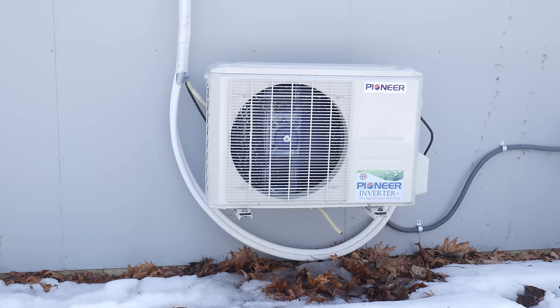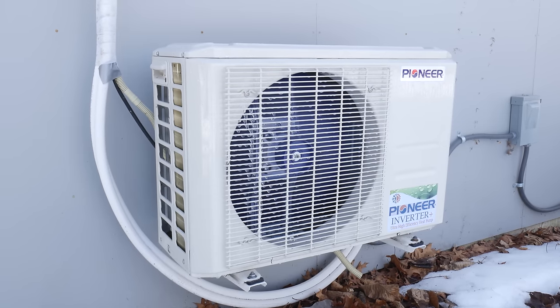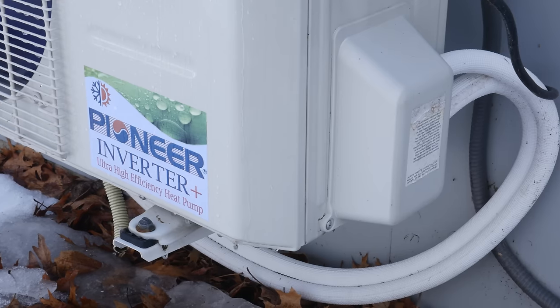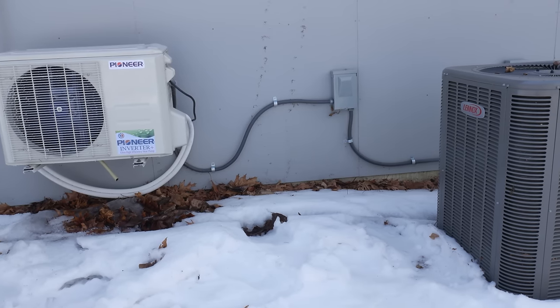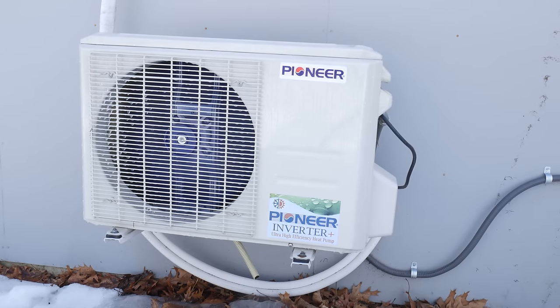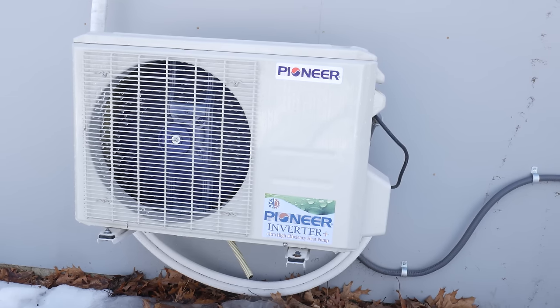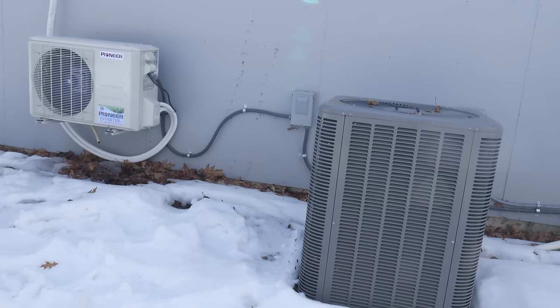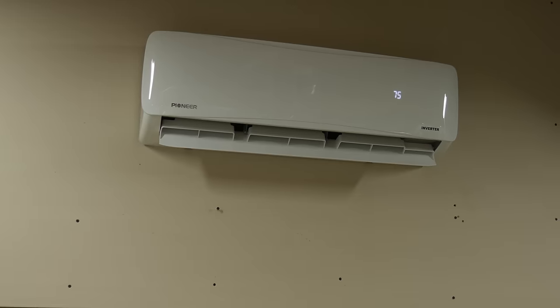Here's a mini-split air conditioner. This is the condensing unit, and inside is a self-contained evaporator and blower. But this is also the evaporating unit, and inside is a self-contained condenser and blower. This is reversible, and so is also a heat pump. This mini-split heat pump system has a different form factor from the central air conditioning system next to it, but mechanically they're something like 95% identical. There are some technological improvements found in the mini-split like a variable speed compressor and more intelligent controls which help it gain efficiency, but fundamentally the heat pump is no different from the air conditioner — it's a compressor, a metering device, a refrigerant line set, two heat exchangers, and a fan of some sort to force air through each one.